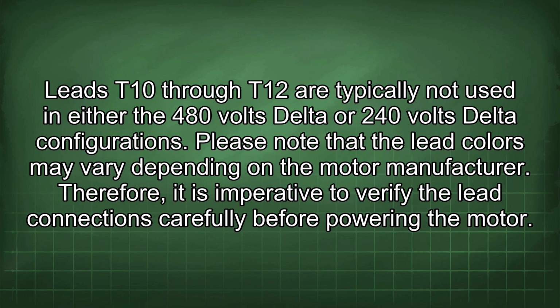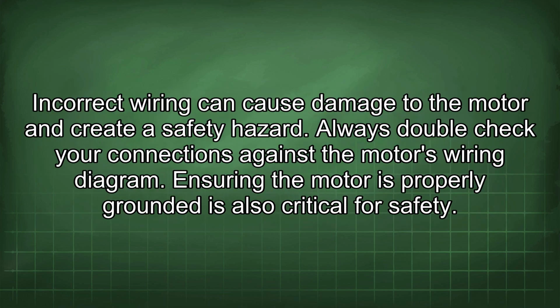Please note that the lead colors may vary depending on the motor manufacturer. Therefore, it is imperative to verify the lead connections carefully before powering the motor. Incorrect wiring can cause damage to the motor and create a safety hazard. Always double-check your connections against the motor's wiring diagram. Ensuring the motor is properly grounded is also critical for safety.